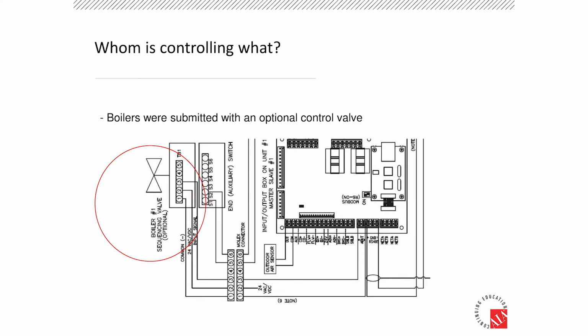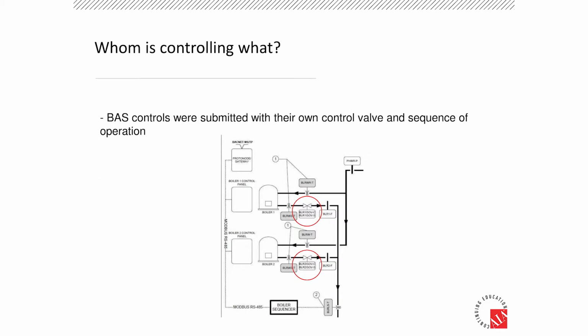So I saw this optional control valve, and I said, okay, I need to find out if this boiler came with this optional control valve. Is that the problem? Is it closing? Is it not opening? What's going on? Then I go to the control submittal and start reading the control sequence of operation, and they very clearly identified on the left-hand side of the drawing, and it might not be clear in the presentation, I apologize, what points were being integrated by Modbus, but what was not noted as being integrated were the boiler isolator control valves that they had command and status over.